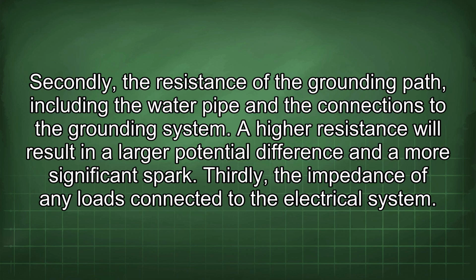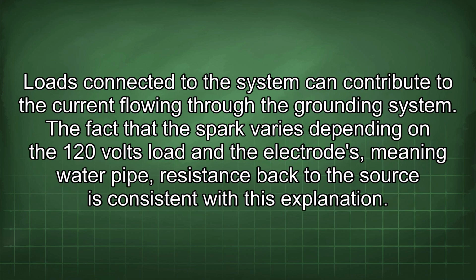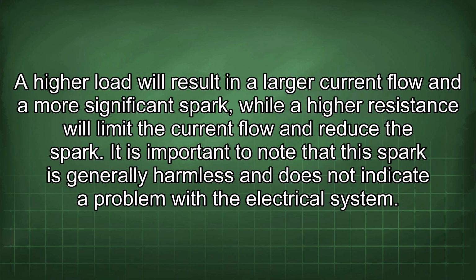A higher resistance will result in a larger potential difference and a more significant spark. Thirdly, the impedance of any loads connected to the electrical system. Loads connected to the system can contribute to the current flowing through the grounding system. The fact that the spark varies depending on the 120 volts load and the electrodes, meaning water pipe, resistance back to the source, is consistent with this explanation. A higher load will result in a larger current flow and a more significant spark, while a higher resistance will limit the current flow and reduce the spark.